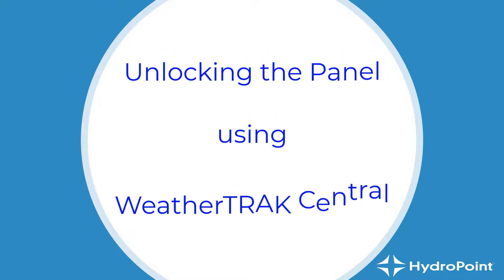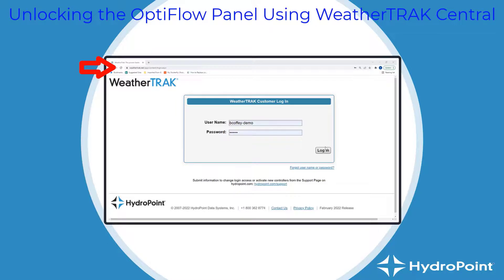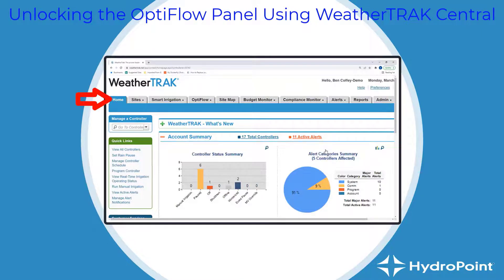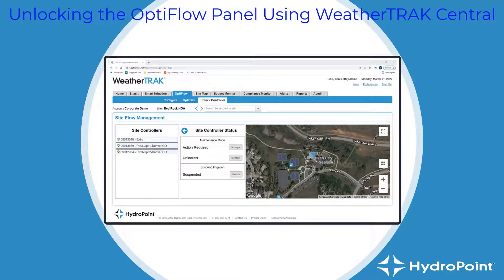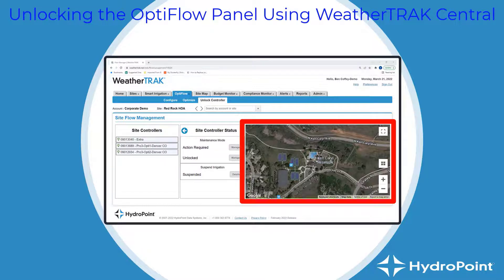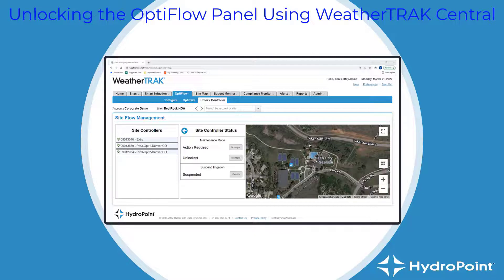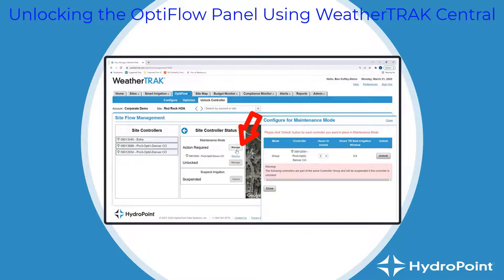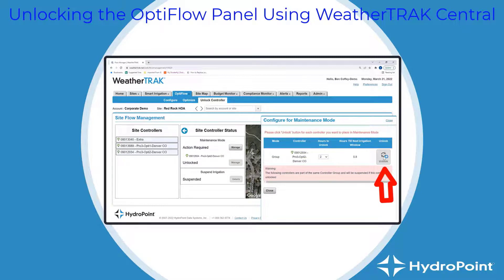If you're helping someone in the field while you're in your office, or managing WeatherTrack.net from your tablet in the field, you might be unlocking the OptiFlow panel from WeatherTrack Central. Go to WeatherTrack Central at WeatherTrack.net and log in with your unique username and password. That brings you to the home page, where you select the OptiFlow tab and then 'Unlock Controller.' First, select which OptiFlow site you want to manage. When the unlock controller page loads, you'll see in the first column all site controllers, in the second column the site controller status, and in the third column the map. The trick is to select the controller you want to unlock and drag it over into the maintenance mode column in the site controller status. As soon as you see it under the 'action required' button, hit Manage, and at that point you can unlock the controller. Hitting the unlock button sends the signal to unlock the controller.